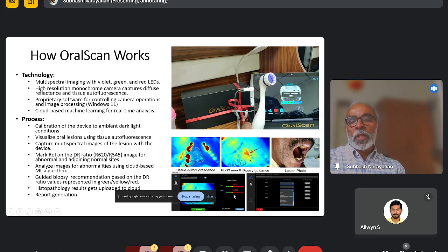You can see in this bottom picture, the green denotes healthy tissue, yellow denotes potentially malignant pre-malignant tissues, and red denotes malignant tissues. So the ROI is marked on the suspicious area, as you can see here, and in an adjoining normal area. This is for comparison between normal and abnormal: how much is the percentage variance of the ratio value? Accordingly, the device will recommend a biopsy, or recommend that no biopsy is needed. Accordingly, the patient can be referred to a hospital for taking a biopsy. And then the biopsy results can be uploaded into the device also for improving the algorithm as feedback.